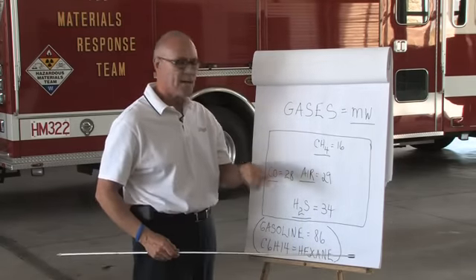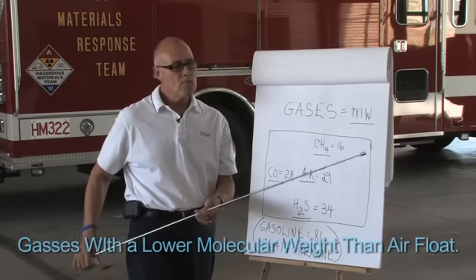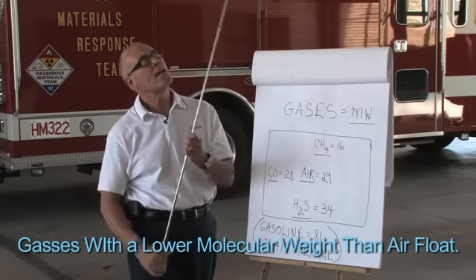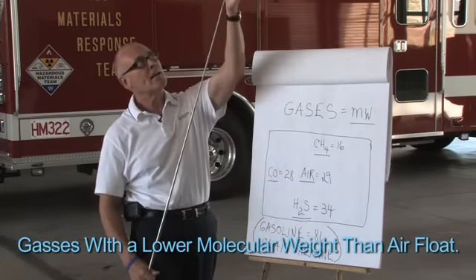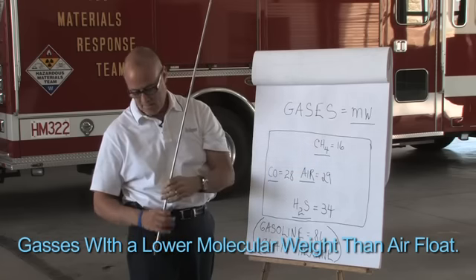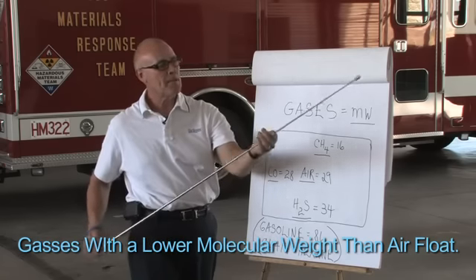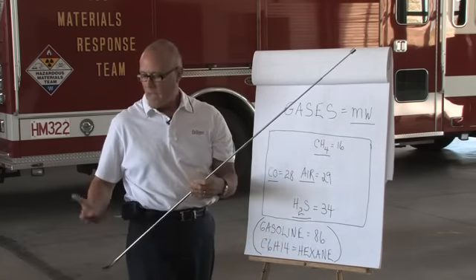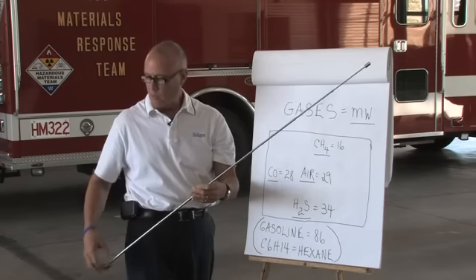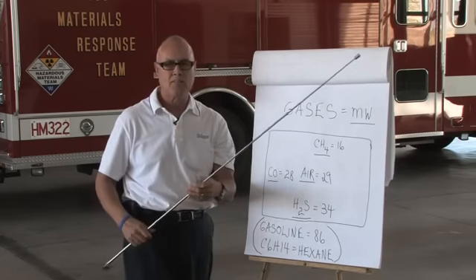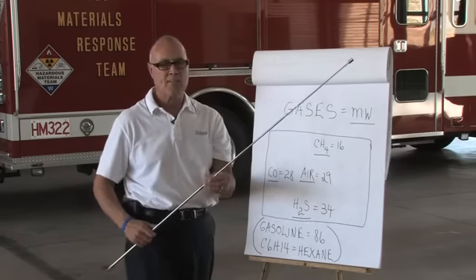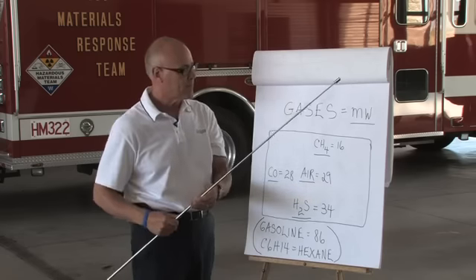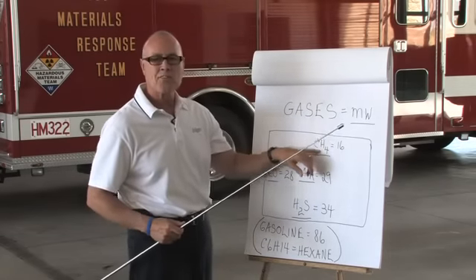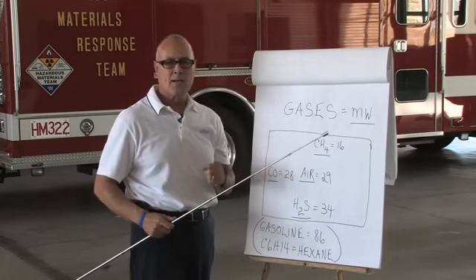It's almost half that of air. So you may have to walk into a structure and go up to the ceiling and have the sample aspirated down, what we call an extendable probe, and wait for the gas to come down the probe through the hose to the instrument.